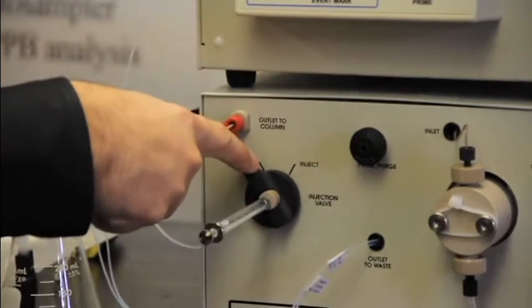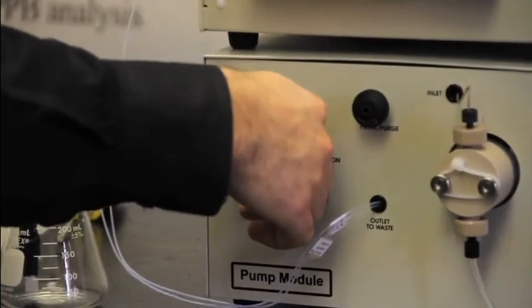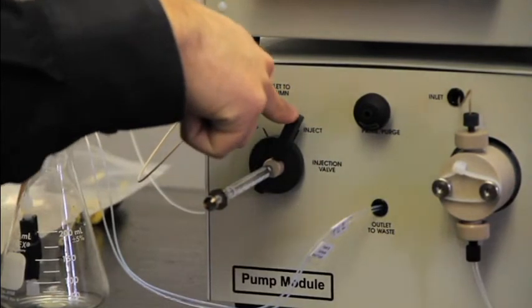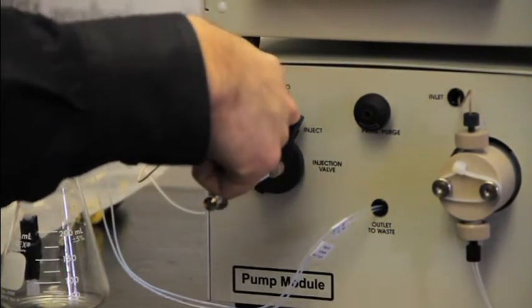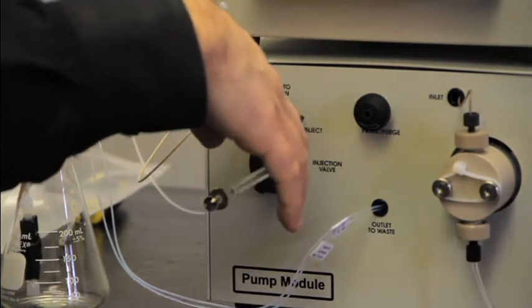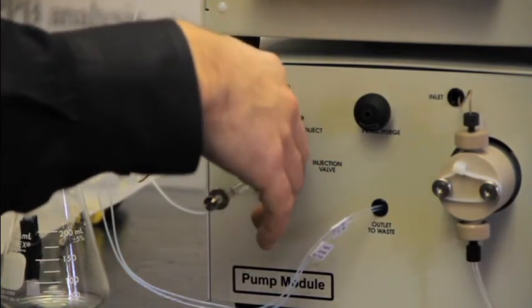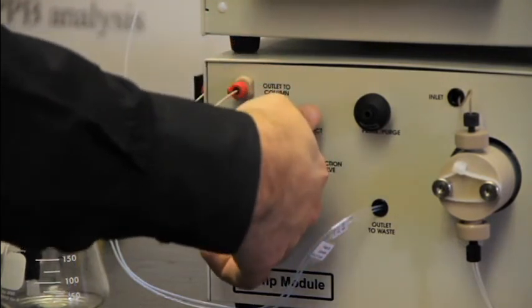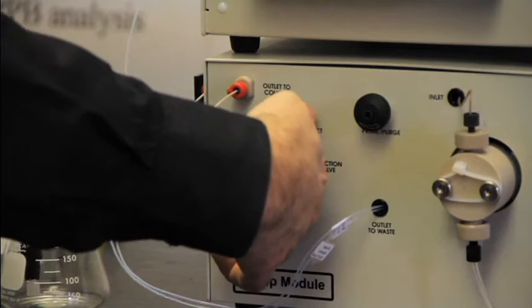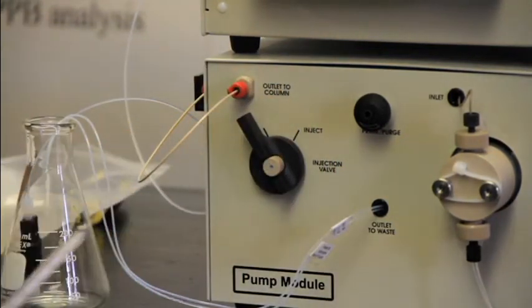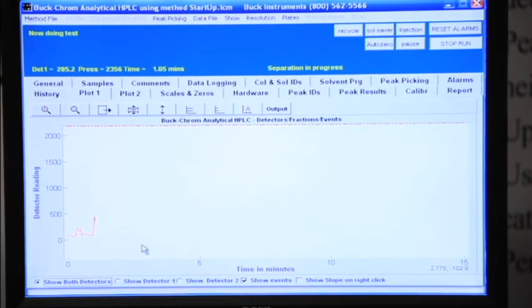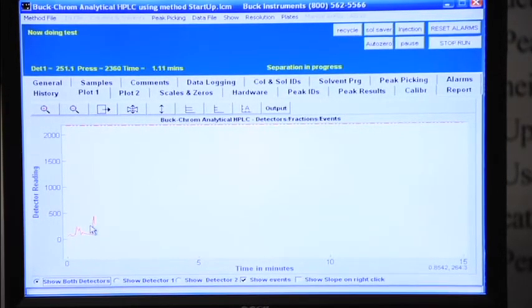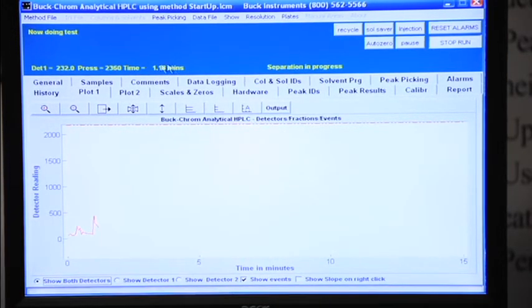At this point, you should turn the valve from load to inject. This signals to the Buck-Chrom software that you've injected, and you should leave it in the inject position for at least 10 seconds to make sure that the sample loop is cleared out. Once you've waited that amount of time, you can turn the valve back from inject to load and remove the syringe. The HPLC will now acquire data through the Buck-Chrom software, and it will run for the amount of time you specified in the General tab. When the time has elapsed, the pump will automatically shut off, and you will be ready to analyze the data.